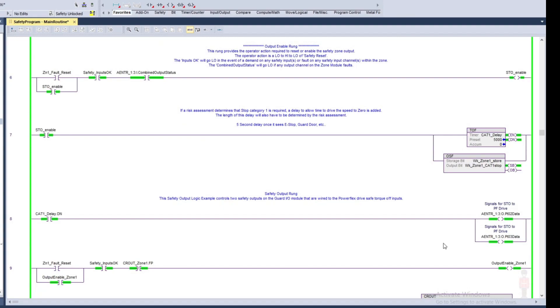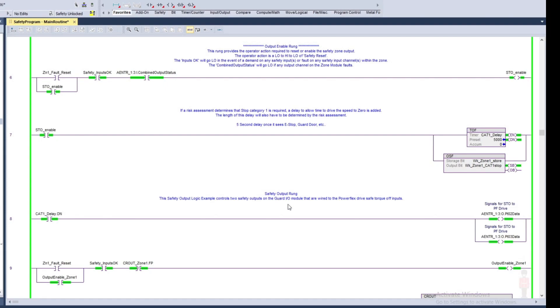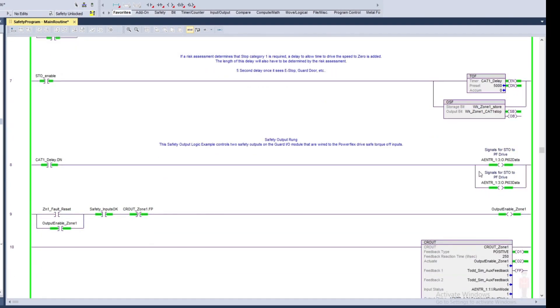In this case I'm doing a stop category one, because when I hit that e-stop condition I want to be able to stop that VFD in a controlled fashion. So in this case I just set up to a five second delay, and after five seconds then I'm going to tell the drive to stop within those five seconds, and then I'm going to also after that take power off the safe torque off so there's no power on the drives.